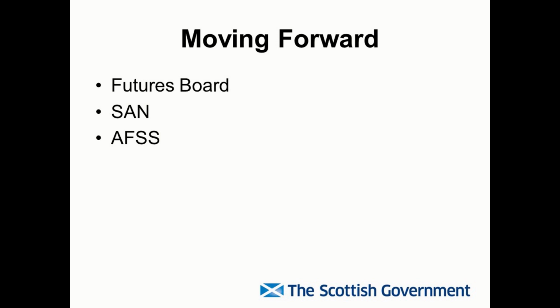Lastly, Building Standard 2.15 currently requires automatic fire suppression systems in residential care homes, hospitals, enclosed shopping centres, schools and high-rise domestic buildings. We're expanding the requirement for automatic fire suppression systems to all flats, regardless of height, and this will be introduced in 2021. The regulations to extend sprinklers to all new flats, maisonettes, new social housing and multi-occupancy residential buildings, referred to as HMOs in 2018 work, will be laid in Parliament, and amendments to the technical handbooks will follow in a few weeks' time.